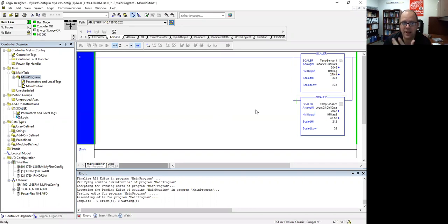But see what I did. I created a logical pattern that is used a lot. I identified inputs and outputs that would need to be there every time it's run. And I set up a function that I can then transport multiple different ways, where all I would need to do is define the inputs and outputs that I set up in my system. If you've worked with Siemens before, this is like a function block. So that's what an add-on instruction can do.